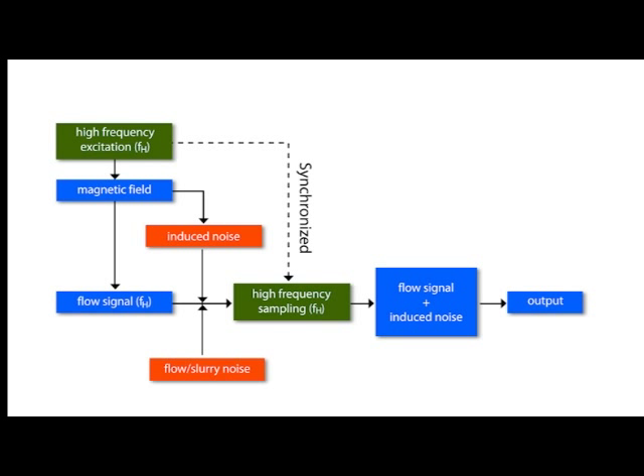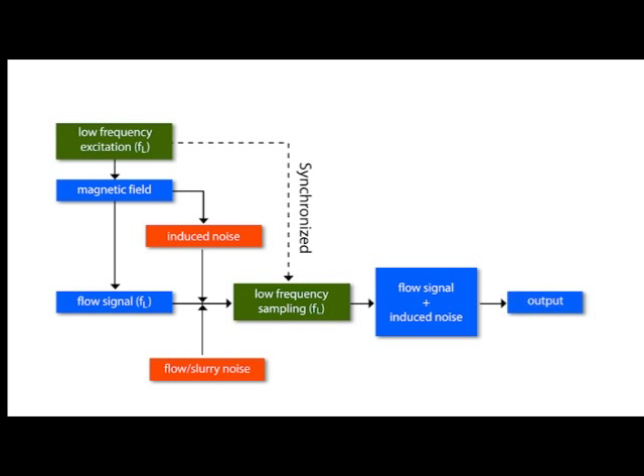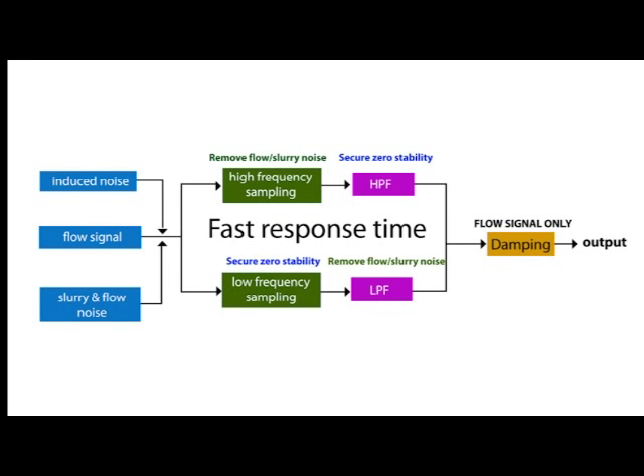In order to eliminate the zero drift problem of an AC magmeter, this output is then high-pass filtered, allowing only the rapidly changing components of flow to pass. The output of the low frequency method provides excellent zero stability, but to eliminate the erratic output that results from slurry noise, it is low-pass filtered, eliminating the slurry noise by damping. The filter time constants are equal in value, but inverted such that when the filtered outputs are summed together, the original flow signal input is recreated at the output, without slurry noise or zero drift.